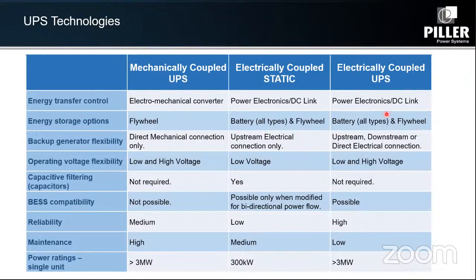The flexibility lies here. With backup generators, we can connect them upstream or downstream through a direct electrical connection. We can build systems on medium voltage or high voltage, going up to 33 kV. We do not have any capacitors inside, which is what I meant about end of life and electronic waste. The system is quite sustainable in that aspect.